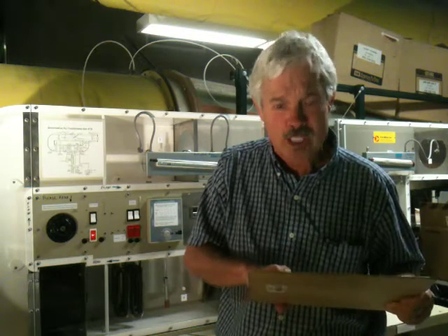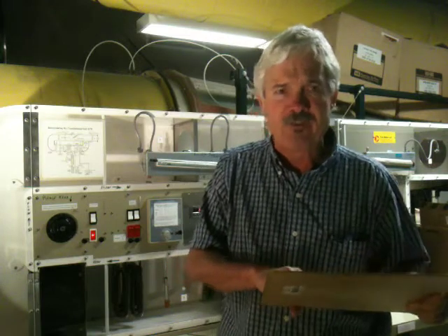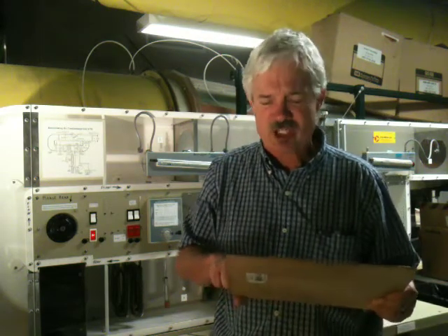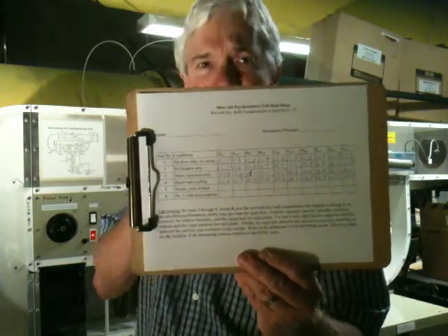Then station D is immediately past the cooling unit, and both temperatures went down from there. The dry bulb went down very dramatically to 15.8 Celsius. The wet bulb went down to 14.8, so now they're very close. We're about 100% relative humidity there. 100% is when the wet bulb and the dry bulb are equal. And then those lower temperatures carried through to station E, close to the discharge. Okay, so there is that data.